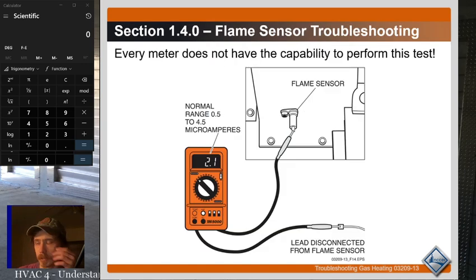A flame sensor is a little different than a thermocouple. A flame sensor is definitely something that you'll want to diagnose with the meter when at all possible, because it's pretty common for the issue to not be the flame sensor and to actually be a ground or a board or something like that. I gotta say, usually, if a flame sensor's dirty, then that's all your problem is. You can clean it off with some light sandpaper or something and get it working.